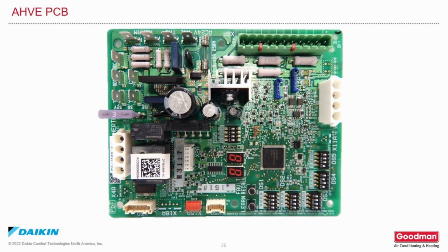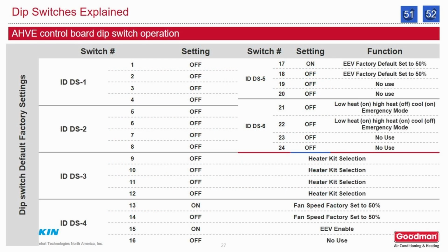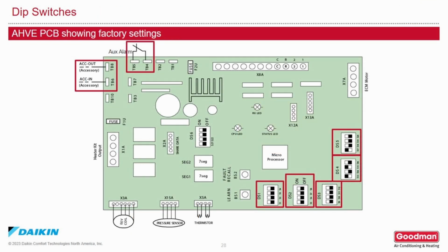Here's an image of the AHVE control board. This shows the placement of the dip switches. This slide explains the control board dip switch operation for the AHVE air handler. It also shows the factory settings for the dip switches. The main dip switches that will need to be field adjusted would be DS3 for your heater kit selection, and DS6 to set the speed of the unit in emergency mode heating and cooling. Here is the layout diagram showing the factory dip switch settings. Refer to the installation manual if you need to make changes.